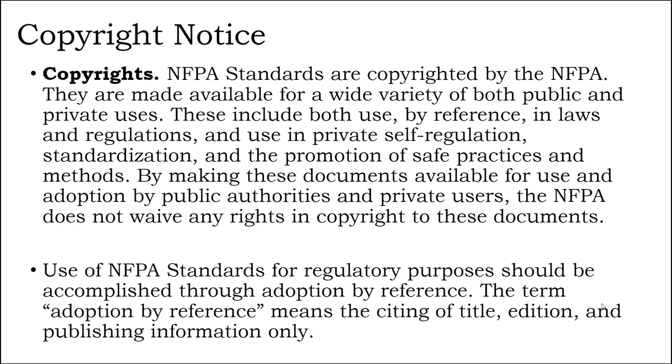If there's an instance where you might think, oh, well, National Electric Code requires this, but should I do something above and beyond what it requires? The answer is, yeah, there could be better ways and even more solid ways to do your electrical design than simply what National Electric Code requires. One case in point I'm thinking about is grounding. There's a lot of different ways to clamp your ground to the ground rod. One way is to weld the connection, and that makes a very tight, solid, not coming apart connection.